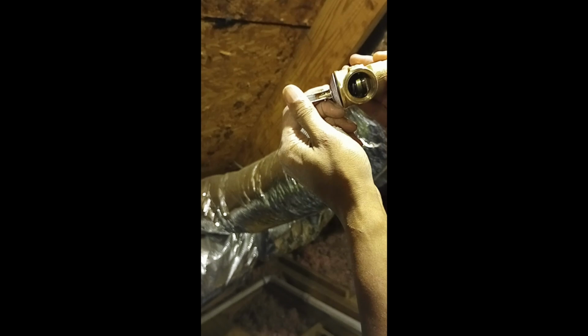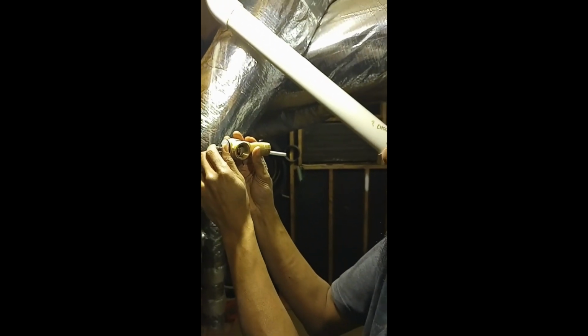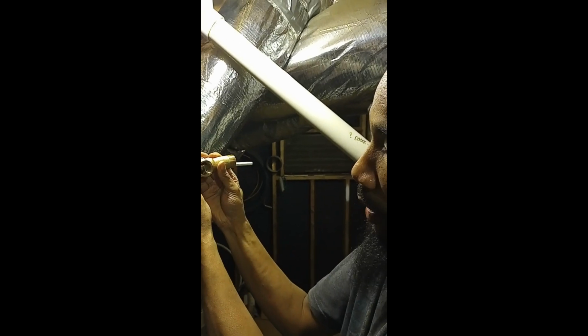Okay. Look at that. So what it does, when I do this, you see that item opening up? I don't know if you get it in the light, but there you go. You see that? So it's closed. That little small cylinder looking piece right there, the cap, is closed. But when it comes like that, you see that gap in there is open. So the temperature inside of that tank will make that spring expand, and it'll automatically make that move. And when it moves like that, it releases the pressure.